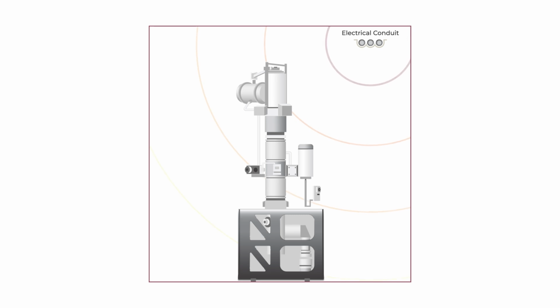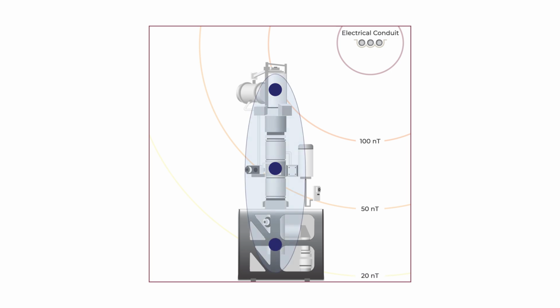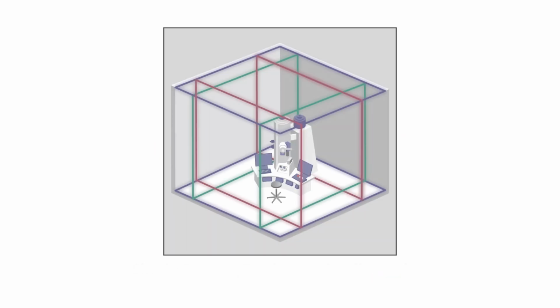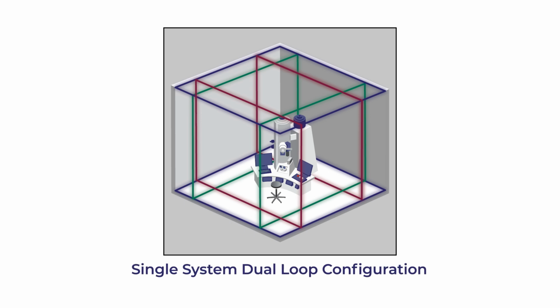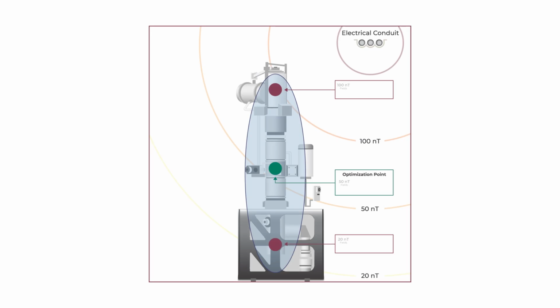So we've talked about the 3 reasons why it's challenging to mitigate both DC and AC magnetic fields for transmission electron microscopes. And it's particularly apparent when it comes to field gradient. Imagine you're in a situation where you have a TEM lab with an overhead electrical conduit, and you have 100 nanotesla of field at the source level, 50 nanotesla field at the sample height, and 20 nanotesla fields at the detector level. Typically with a single dual loop cancellation system, VEC will optimize the field cancellation system at the center of the microscope and try to provide uniform cancellation along the electron beam column.